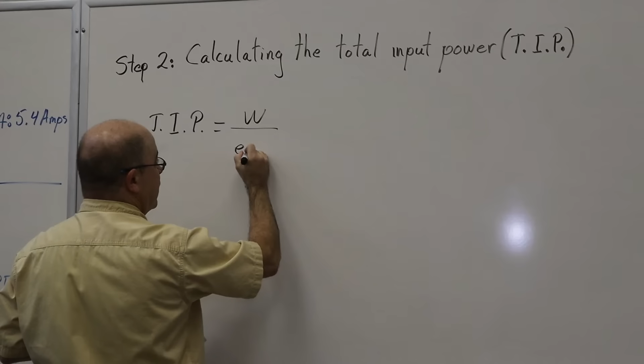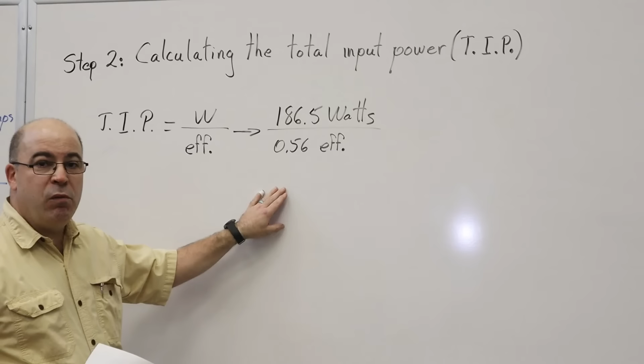it's equal to your watts divided by the efficiency of the motor. So in this case, we're going to take what we just calculated, which was 186.5 watts, and we're going to divide it by the efficiency. Now the efficiency, if we don't remember, it was 0.56. I had to convert this into decimal form in order to do the calculation. I couldn't put percentages here.